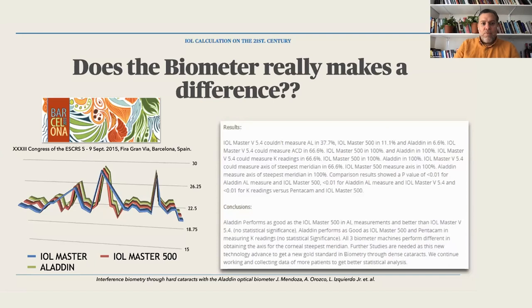At the ESCRS held in Barcelona in 2015, I and a group of colleagues presented a paper doing a similar comparison. We compared three optical biometers — IOLMaster, IOLMaster 500, and the Aladdin — and the conclusion was that these three biometers performed equally well, except the previous IOLMaster version, which lacked the composite signal that IOLMaster 500 has. When the peaks obtained by the biometer are not good, biometry won't be accurate — and that's a critical issue with dense cataracts.